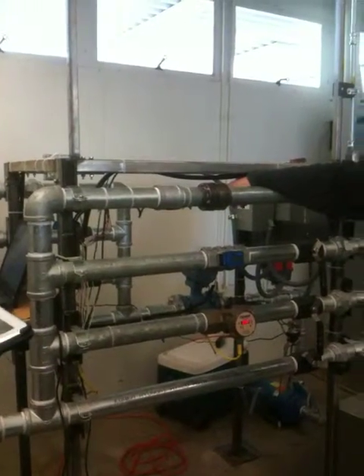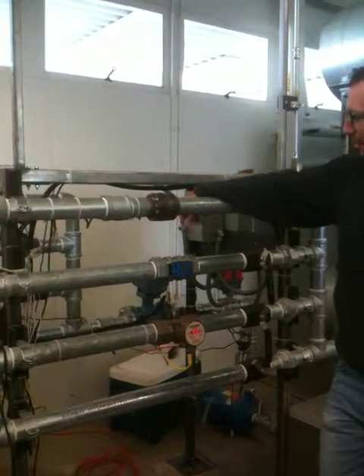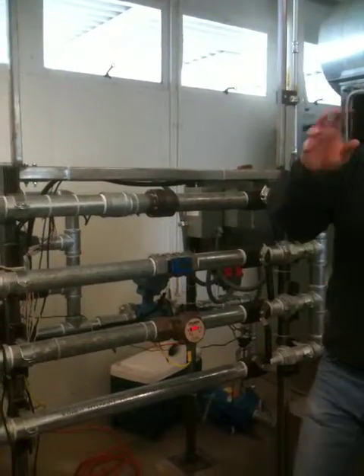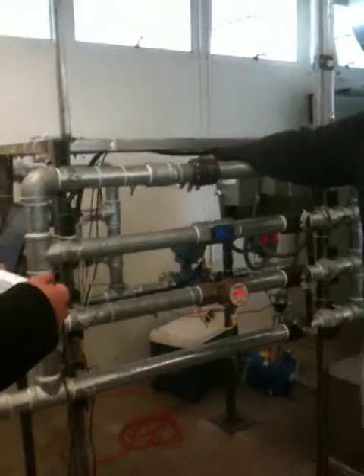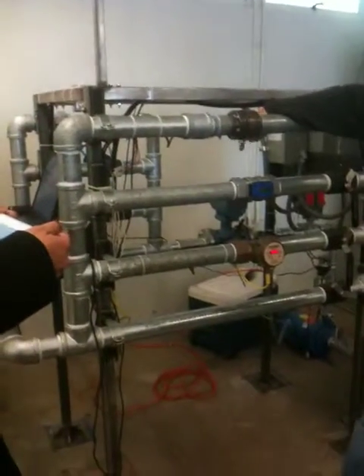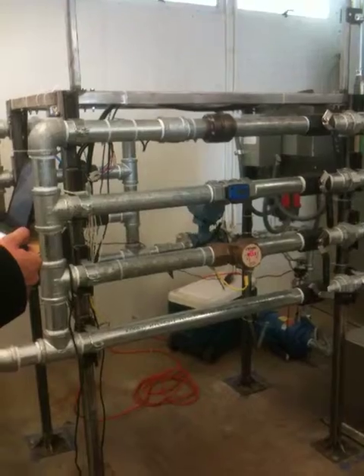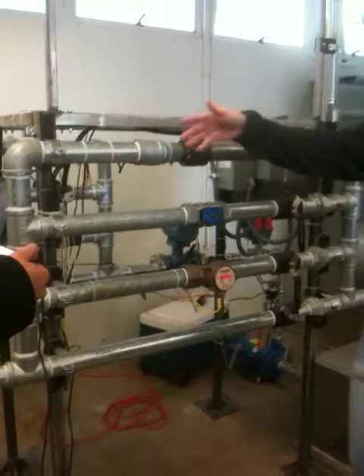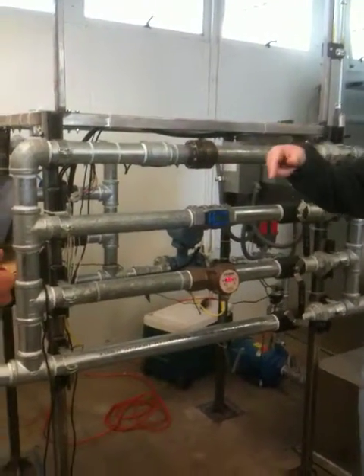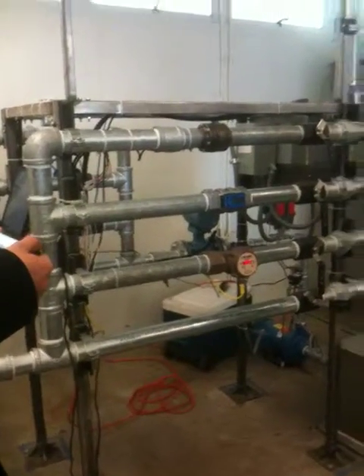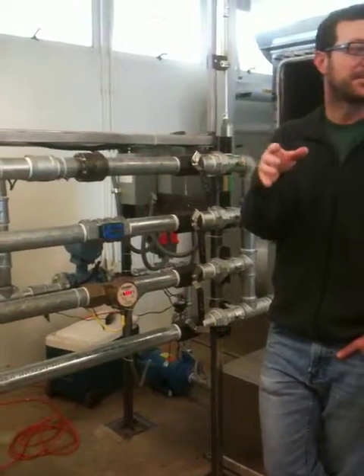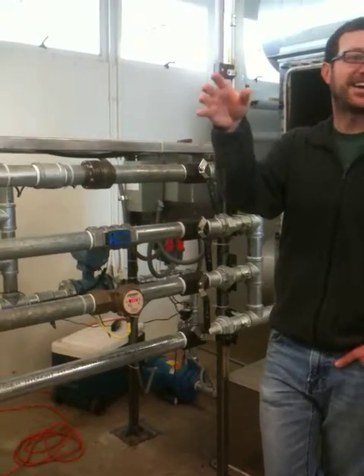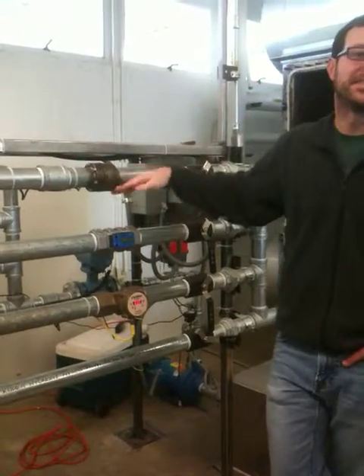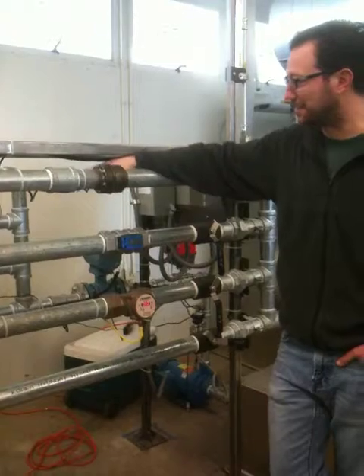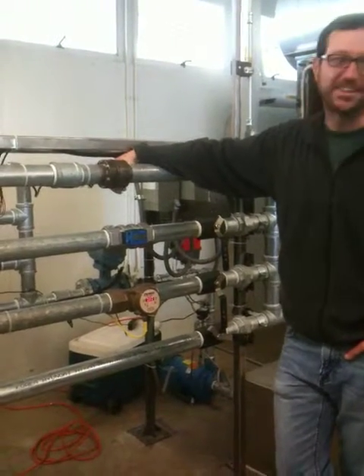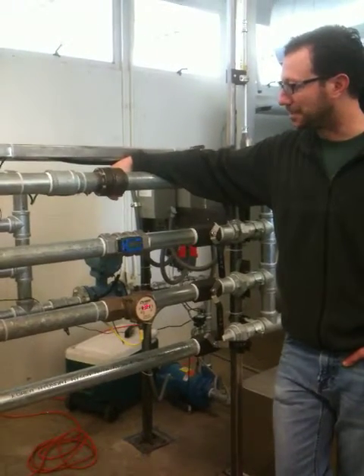That's sort of a challenge to get because you have all these other things. So I would just set the flow so that you're a little over 1 psi between those two, and then keep increasing it. So get maybe 4 or 5 points until you get, say, 4 psi through that entire branch. And then when you subtract out all the other stuff, you'll see here it is at 0.7, here it is at 1.5. So we think this is the flow coefficient. That's the best you can do because we don't have it measured directly right at the valve. But that's pretty much it.